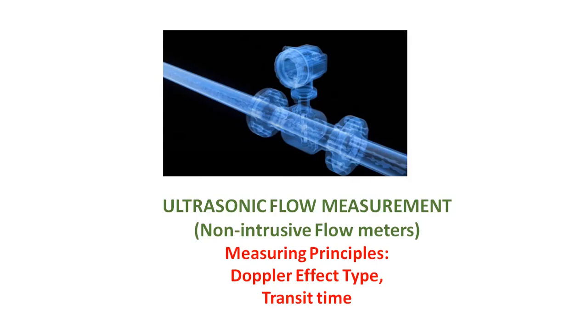In this video I will discuss the ultrasonic flow measurement technique. Ultrasonic flow meters are non-invasive flow meters, which means there is no restriction in the flow path. Unlike orifice flow meters, which use a restriction that causes unnecessary losses due to pressure drop, this is the key advantage of the ultrasonic flow meter.